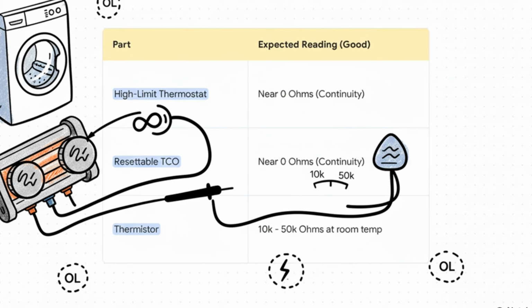You've got two thermostats, and both of those should show continuity, which looks like a reading close to 0 ohms. Then there's the thermistor, that's just a fancy name for the temperature sensor. It should read somewhere between 10,000 and 50,000 ohms. If any of these parts read OL, you found your problem.